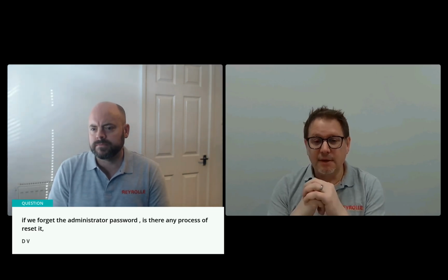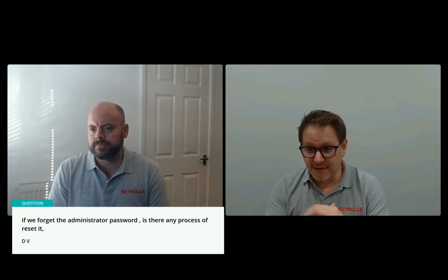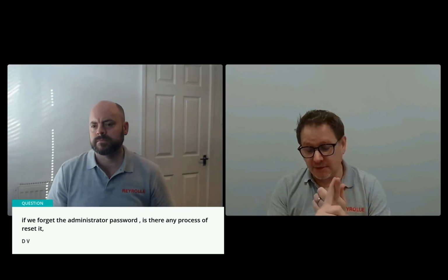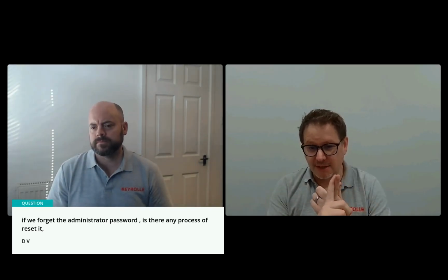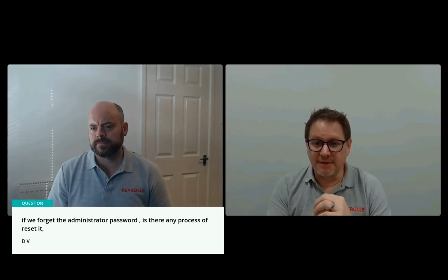You press that and the login for that is 6 zeros. You press the 6 zeros and then that will reset the RBAC security. Don't forget all the security settings are erased and all the users in the user database are erased. It's very much a last-ditch recovery mechanism in an emergency to get back control of your device.